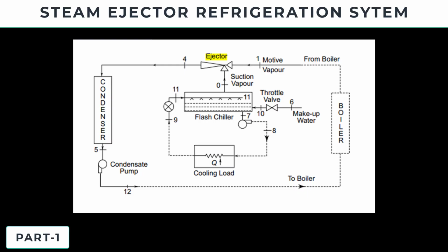Now, the system is often driven by waste heat coming from solar heat energy, or from a boiler, or it can be heat coming from an internal combustion engine. So that makes it very practical and economical for certain applications. It is less efficient than the conventional vapor compression system.